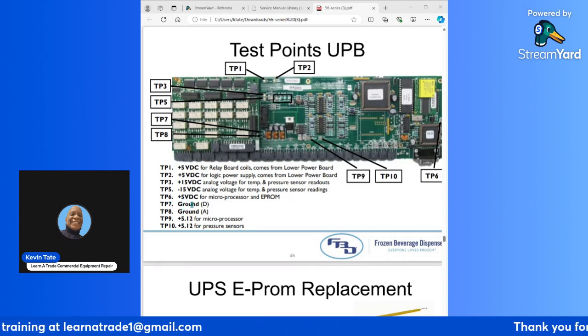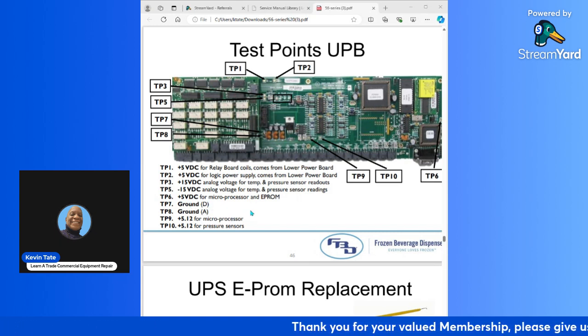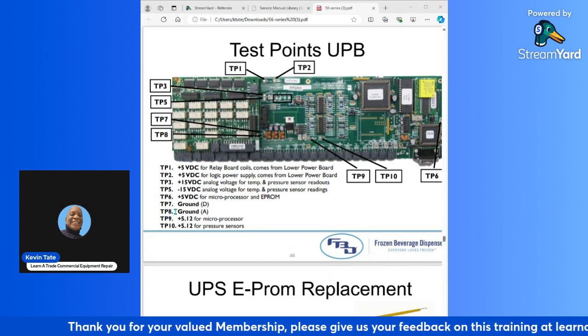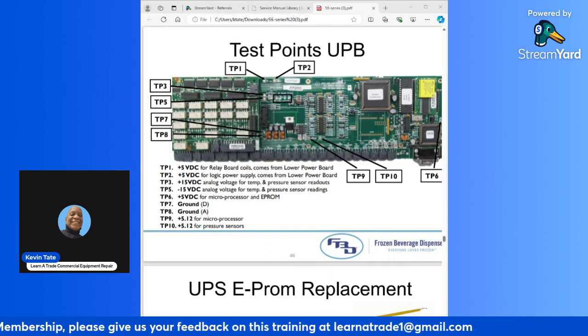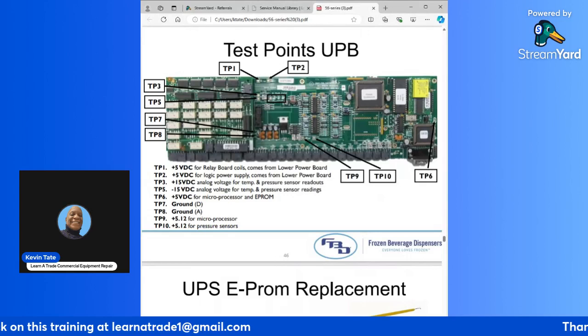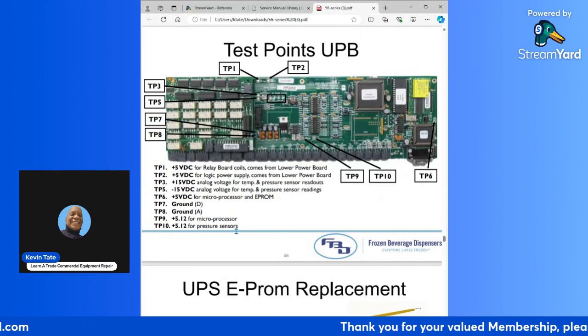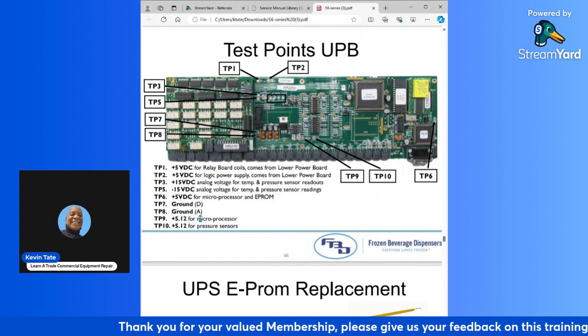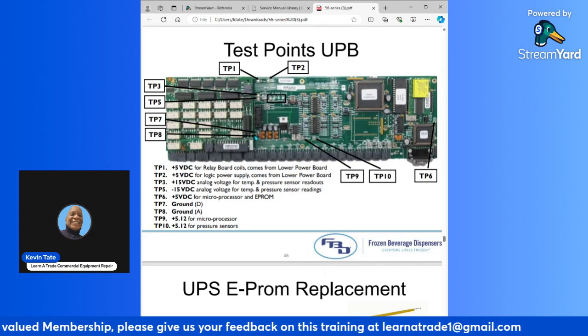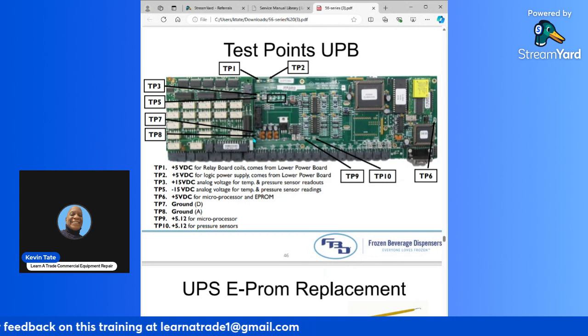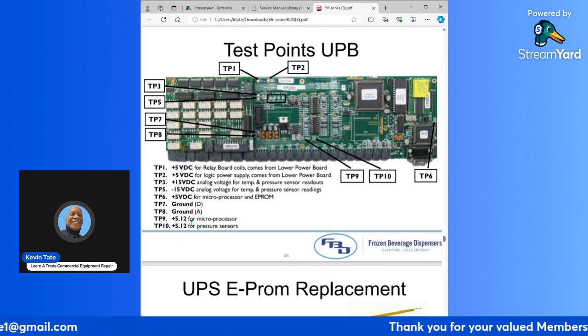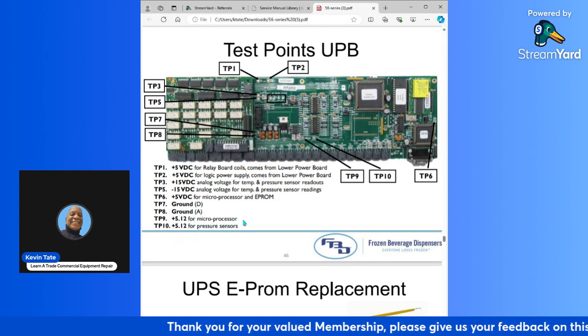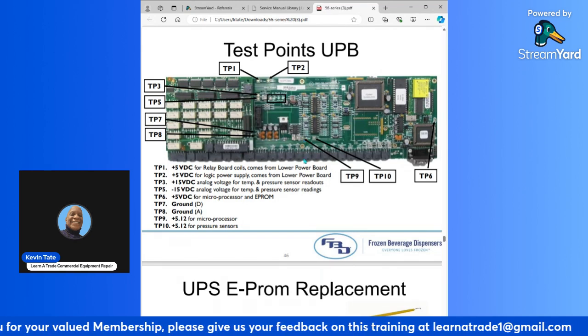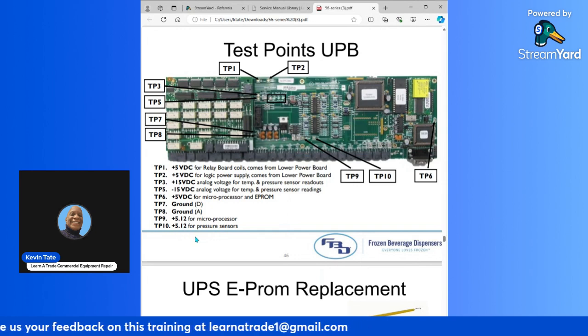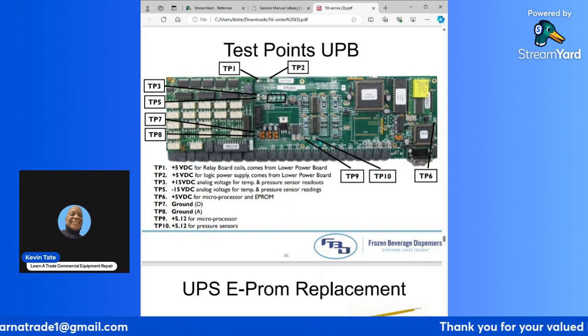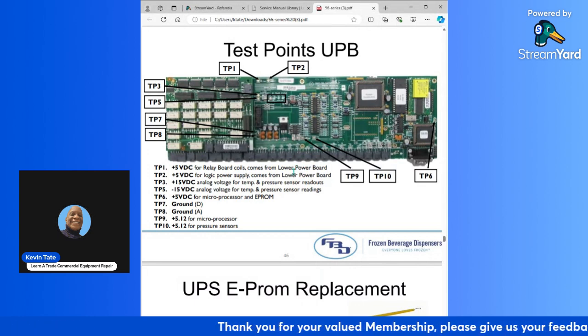TP6 is plus 5 volts DC for microprocessor or EEPROM. TP7 is your ground right here. You see it right there. TP8 is your ground A. That's right here, just below the TP7. TP7 is your ground D. TP8 is your ground A. TP9 plus 5.12 for a microprocessor. That's right here. That's your test point. TP10 positive 5.12 for pressure sensors. That's for your pressure sensors. So those are all of your test points on this upper board.